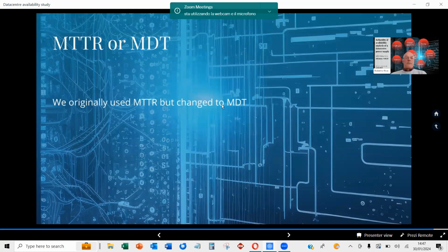So that finishes the last metric, which is MTTR. Originally, almost by default, we configured our blocks on MTTR, mean time to repair. But then we realized the standard IEEE 493 also had a mean downtime metric, which was actually more useful, because in some cases a repair was taking place for 7 hours, but the downtime was only 5. We were concerned only with the downtime of our system, not really with the cost of the repair, so we didn't care whether it lasted 7 hours if the downtime was only 5. We then reversed everything back to mean downtime and reconfigured the system for all mean downtime values.